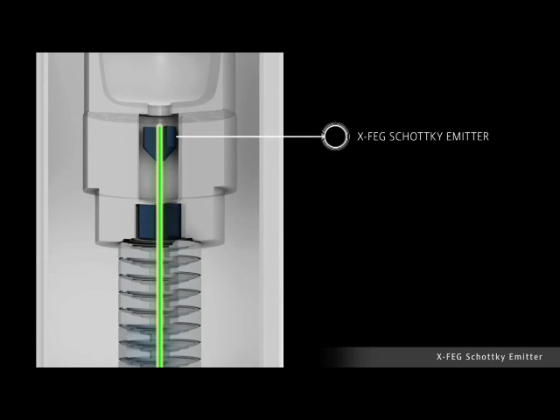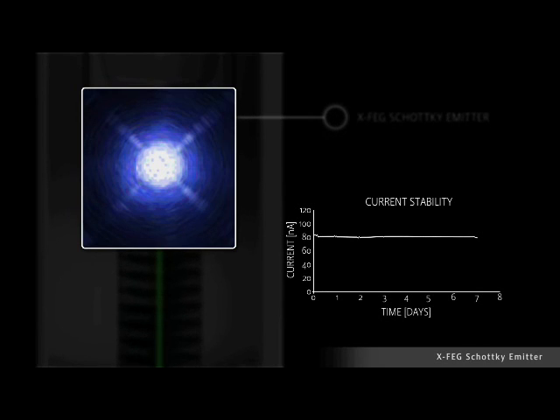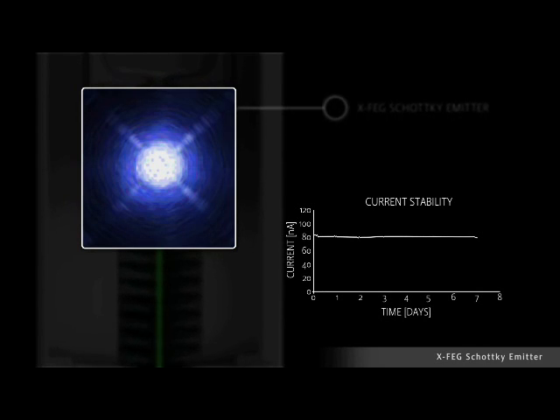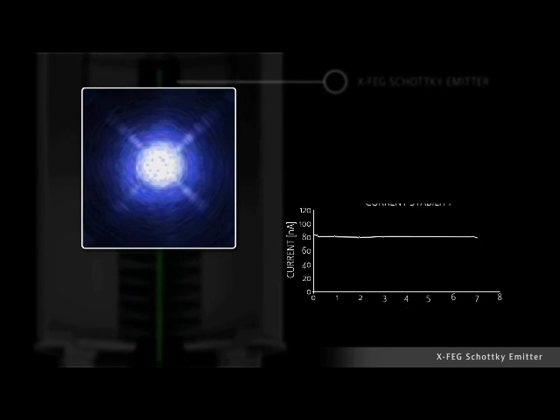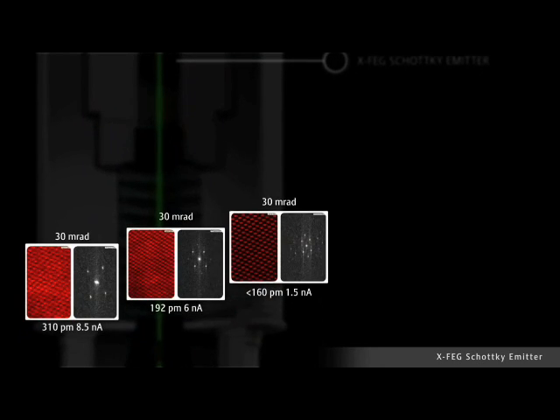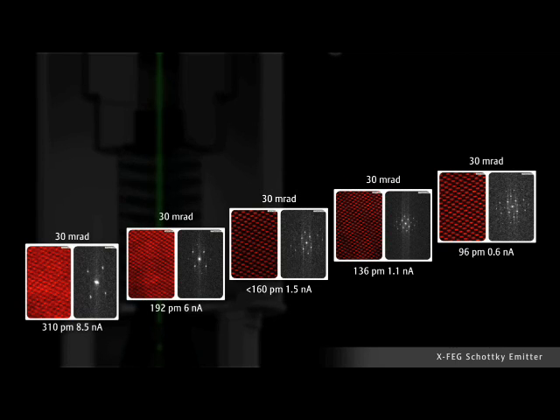The XFEG electron gun delivers high coherence and brightness that is coupled with high emission stability to produce stable measurement conditions not just for hours but greater than 1% emission current stability over a week-long period of operational use. The extreme high brightness offers high beam currents in atom-sized probes for the acquisition of fast and reliable atomic images and chemical maps.